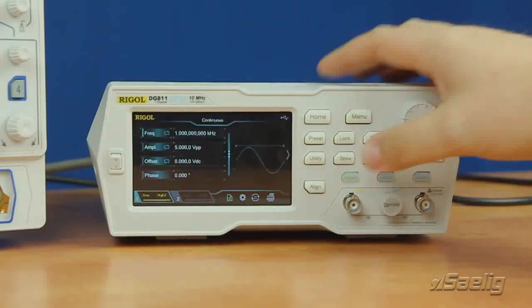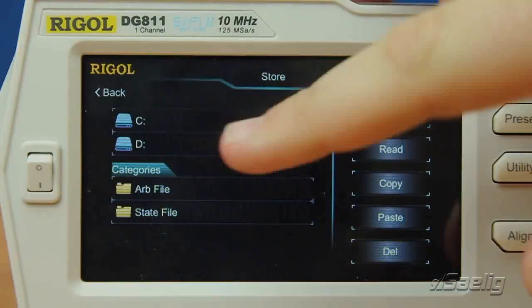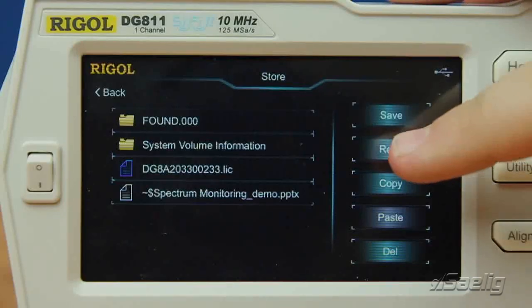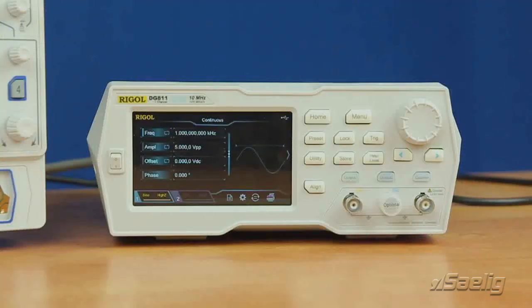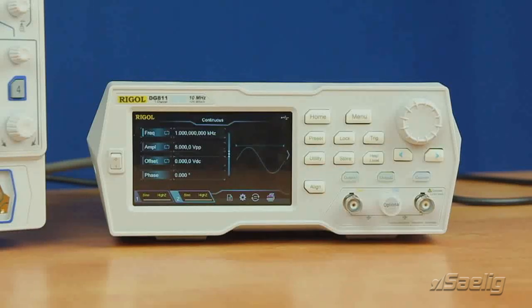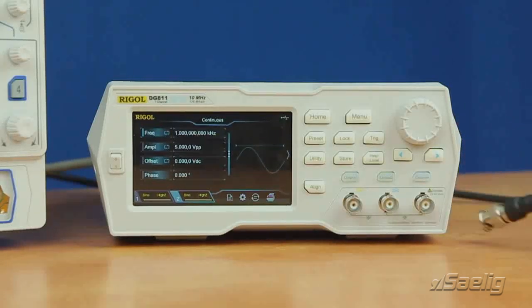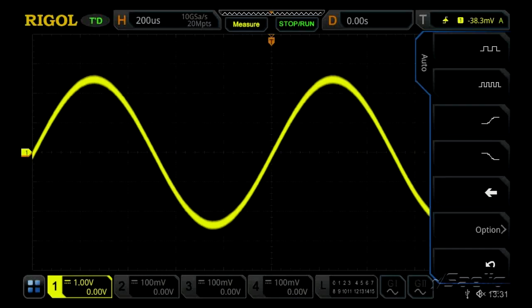Now that we've loaded the license file onto a flash drive and inserted it into the back of the instrument, we press the storage button, select the D drive — our flash drive — and select our license file. Press read and this will read the license. Now that the license has been activated, we can turn on channel 2. To prove it's working, we've connected a BNC cable to our oscilloscope and connect that to channel 2 — and we'll see a sine wave on our oscilloscope.